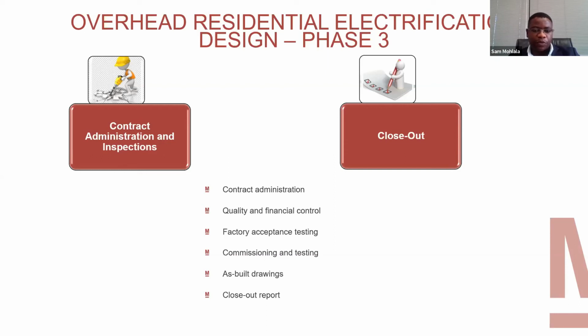That's where your project is under construction and you do factory test acceptance of the equipment, commissioning and testing. When the equipment is transported to site and installed, it has to be tested again to ensure there's no potential damage from transporting. Before energizing the equipment, we have to be 100% sure it's satisfactory according to the standards it was designed at.